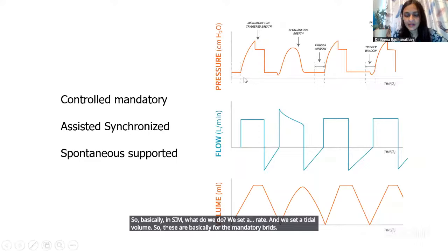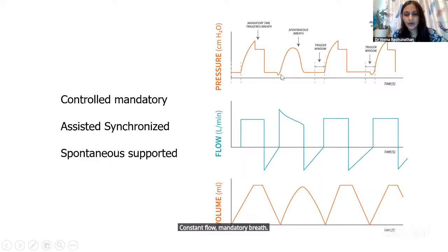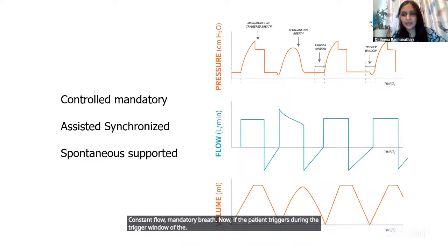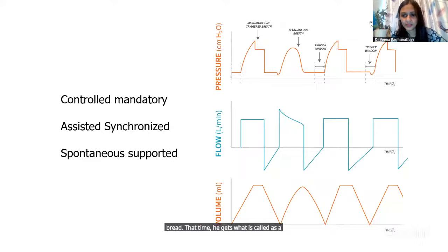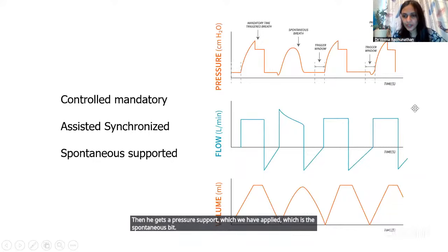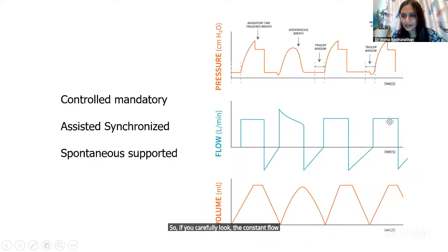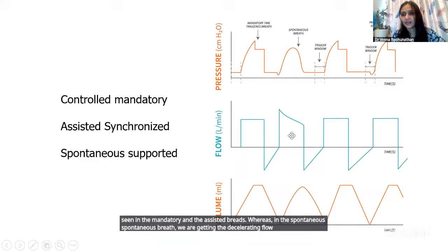So if we see in this graph, the first breath which is getting delivered is a constant flow mandatory breath. Now, if the patient triggers during the trigger window of the breath, that time he gets what is called an assisted synchronized breath. So this is the second type of breath which can happen in the SIMV. And then in between, if the patient is breathing, then he gets a pressure support which we have applied, which is the spontaneous breath. So if you carefully look, the constant flow is seen in the mandatory and the assisted breaths, whereas in the spontaneous breath, we are getting the decelerating flow because we are applying the pressure support.